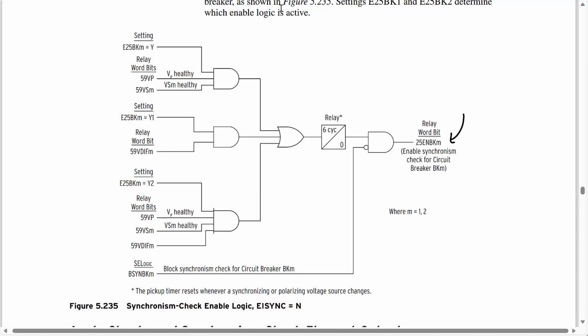Now again, we can see over here that we have basically 3 options given by these 3 AND gates over here. And you can see that which one of those options we use depends on the setting that we just talked about, E25BK1. So we can set that to Y, Y1, or Y2. Now, if we set this element to Y, the relay makes sure that both the line side and the bus side voltages are within a healthy window, which we can of course set in the settings file, and we're going to set those to be some percentage above or below the nominal voltage.